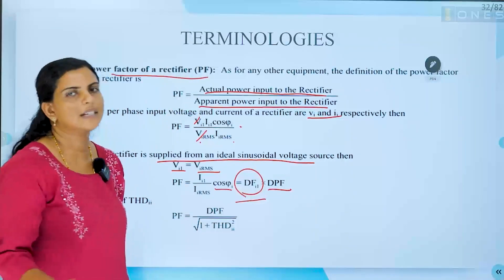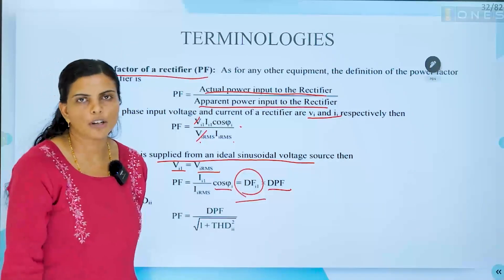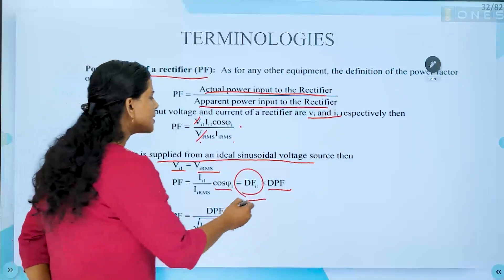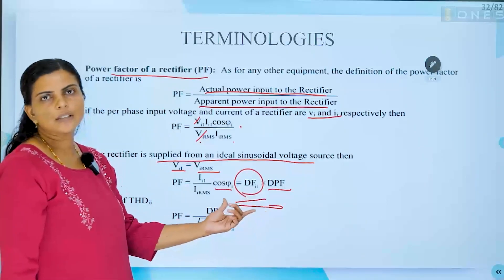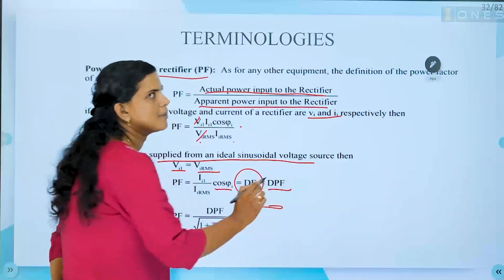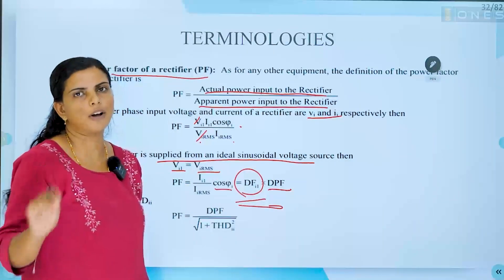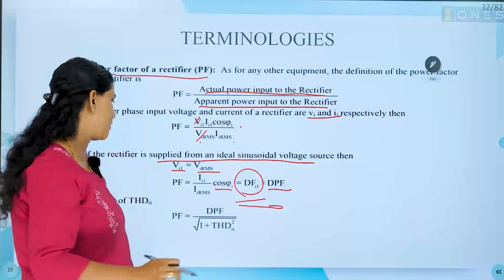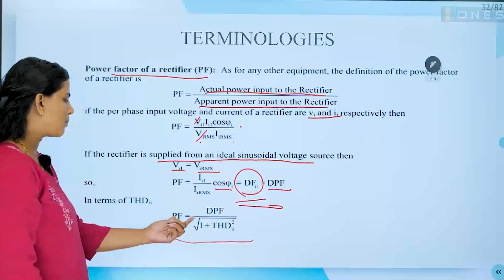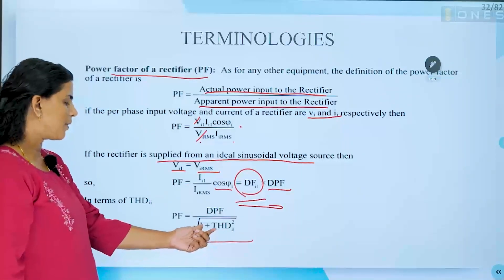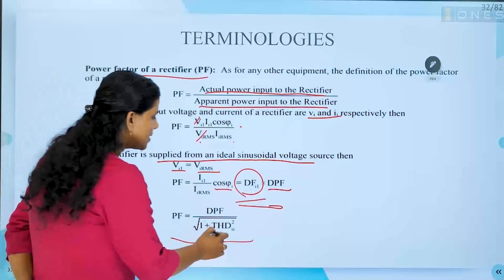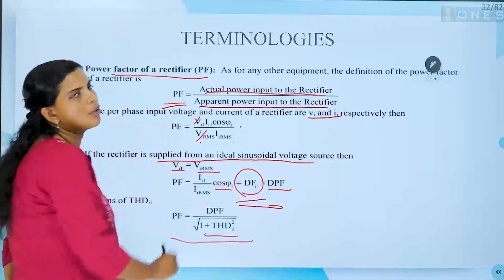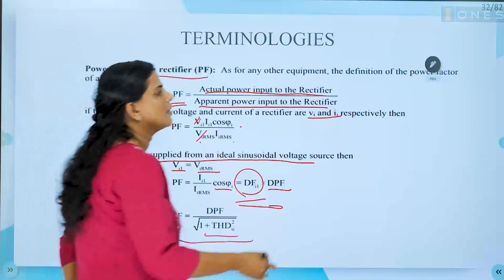The distortion factor — that is the harmonic factor — comes into picture when we have non-linear loads. Power factor is never equal to displacement factor alone. Saying power factor equals cos φ is wrong. Power factor equals true power by apparent power, or the product of displacement factor and distortion factor. Power factor in terms of THD equals displacement factor divided by the square root of (1 + THDi²).